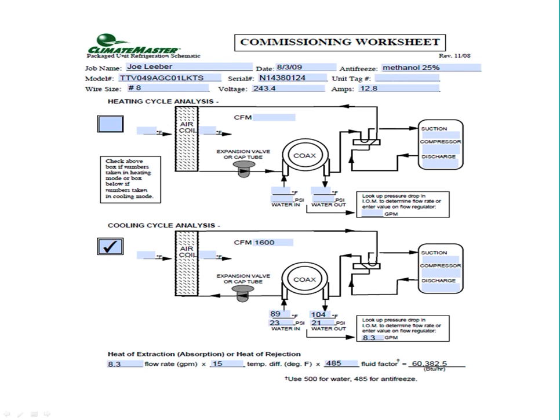Well, what are we going to do? My recommendation is this likely has 2 pumps on it. If you got 2 pumps on it, I would do an amp draw on each pump, and I would compare that amp draw to the electrical tag on the end of the pump. I'll show you a couple of pictures here coming up. My guess is you may find that you've lost a pump.